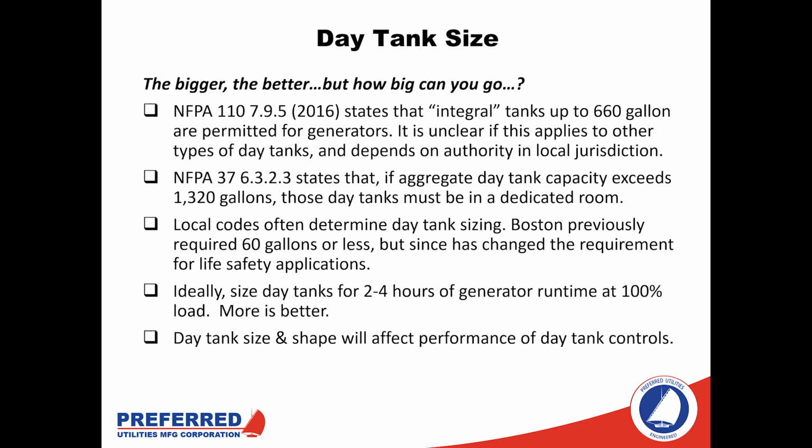Now, moving on to day tank sizing. Again, this is the tank that's located at the generator, sometimes called a belly tank, depending on its size and location and configuration. And we're going to take a closer look at the tank itself and how we would select and design it. But right now, for the amount of fuel that we need this tank to store, it's very important because this is the tank located at the generator.